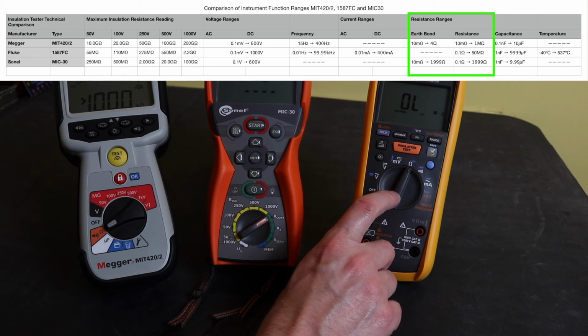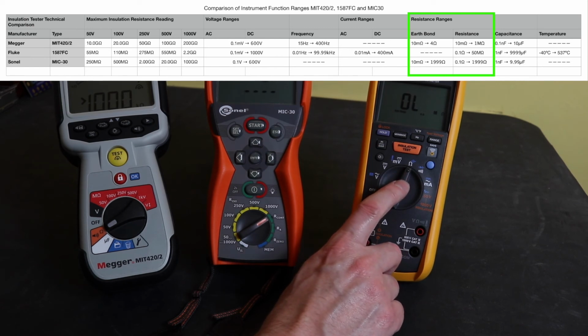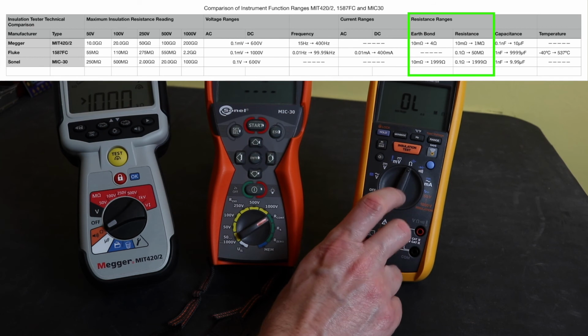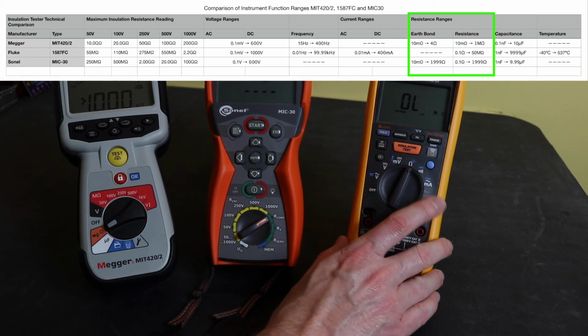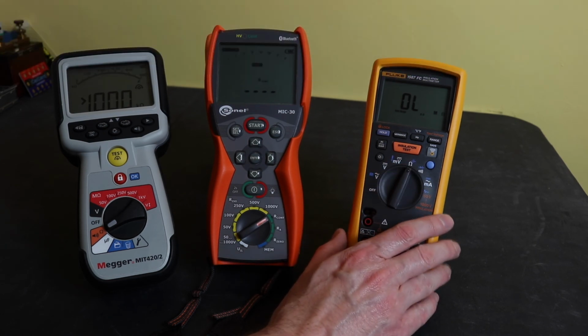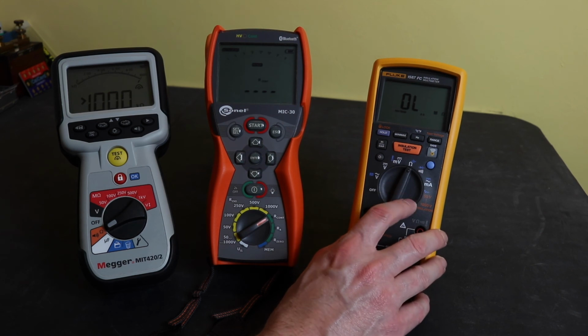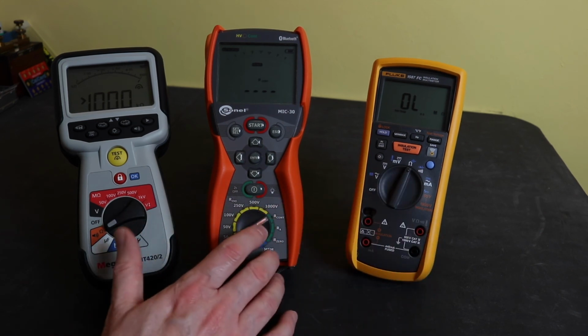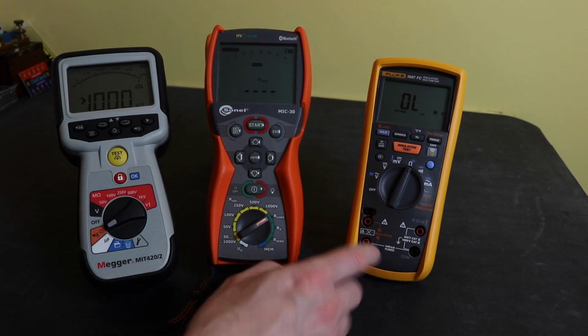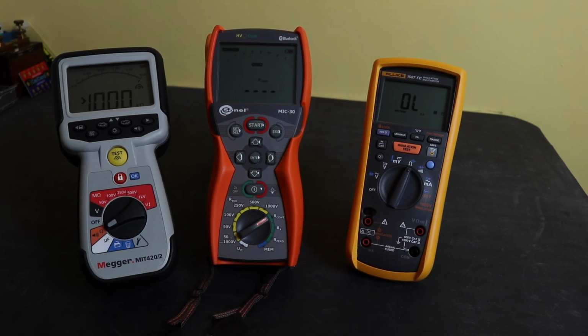For the Fluke here, you have the ohms that will measure from 0.1 ohm up to 50 mega ohms, so much wider resistance range reading, but you have no 200 milliamp test facility that you use for earth bond testing in my country. So in that sense, the Fluke loses out to the other two instruments.